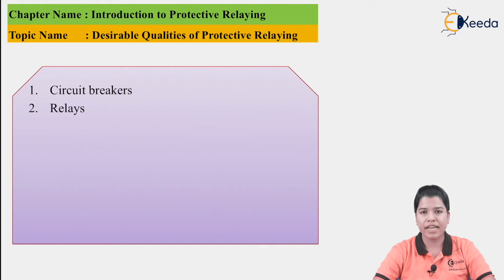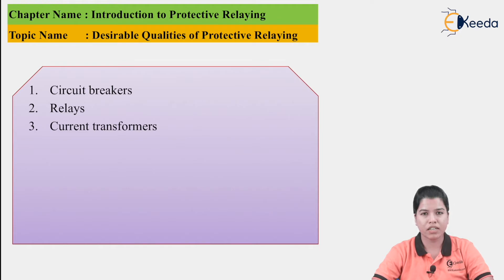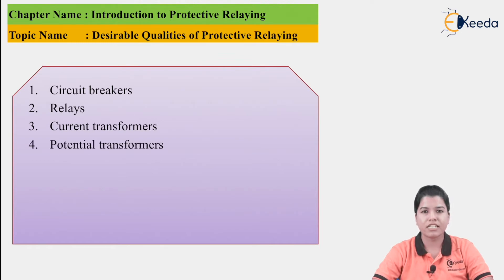Next is Relays. The relay is fed with a certain actuating quantity. If the current goes beyond that actuating quantity, the relay must send a trip signal to the circuit breaker and the contacts of the circuit breaker will open. Next are Current Transformers. Current transformers sense the current; the secondary winding is connected to the relay. Whatever current is sensed by the CT is sent to the relay, which detects whether the current is normal or abnormal and gives a signal to the circuit breaker.